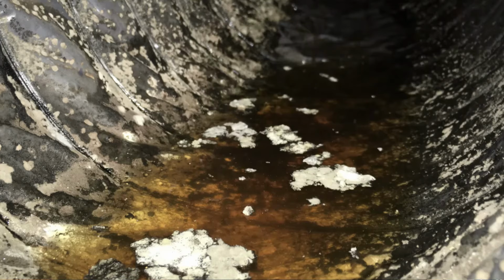The second one I want to talk about is the nastiness inside the crawl space. The coil flooded. It had a dirty filter. It froze the coil. The coil then thawed, and the water overflowed into the crawl space, down the duct, and it sat there. And it sat there for a very long time. Customer's complaint was it was starting to smell inside the house.